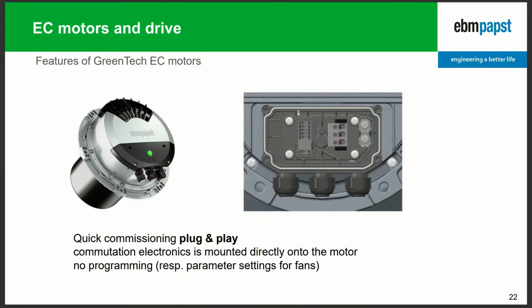This is something that is not generally available, to have motors with an implemented drive system. That makes the unit compact. It makes it easy to handle. So you don't need a connection between a VSD and the motor. You don't need to use shielded cables, which are required when you use an inverter. And it makes the product easy to use in the application.